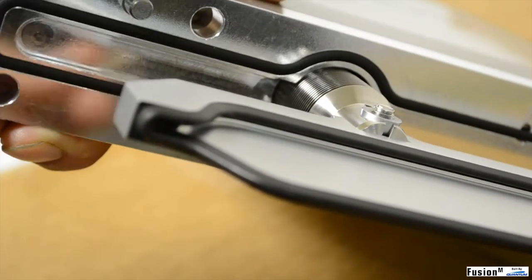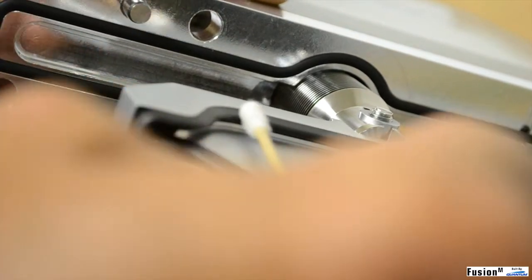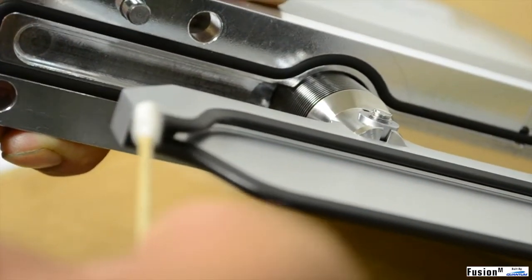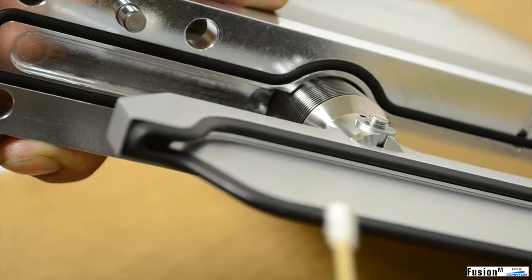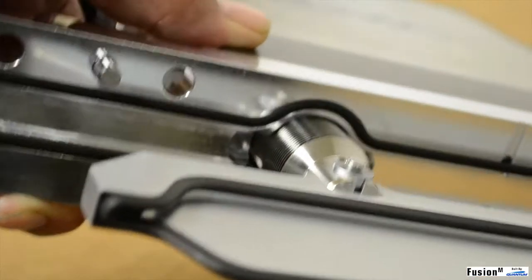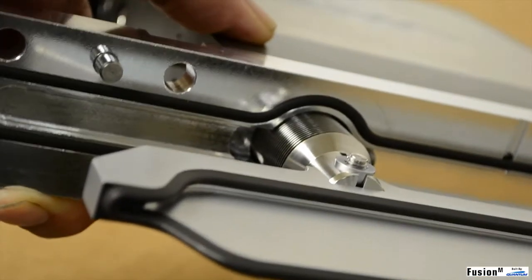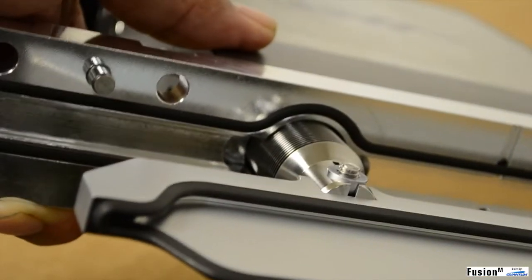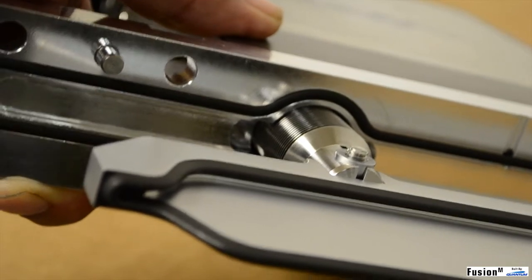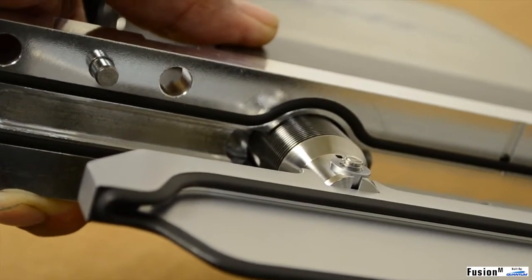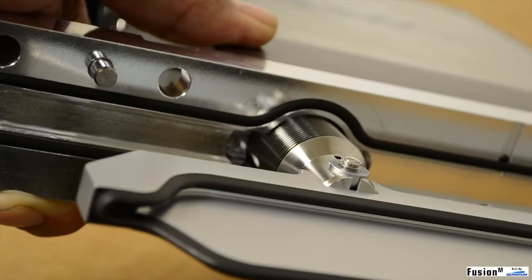It comes up here and does a U-turn, comes over the top of the blade. This allows this particular seal to seal both sides so you can run vacuum on one chamber, atmosphere on the other, and then you can reverse that and the seal will hold up. That's what it's designed to do.